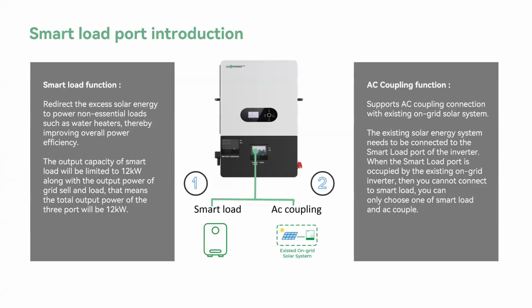We mentioned before in the interface introduction that we have a smart load port, which is different from our other models that use the GEN port as both generator input and smart load and AC couple function. But for the SNA 12K, we have a separate smart load port. Through this port, we can achieve the smart load function and the AC coupling function. With the smart load function, we can redirect excess solar energy to power non-essential loads such as water heaters, thereby improving overall power efficiency. The output capacity of the smart load will be limited to 12 kilowatts along with the output power of the grid side and the loads, which means the total output power of the three ports will be limited to 12 kilowatts.